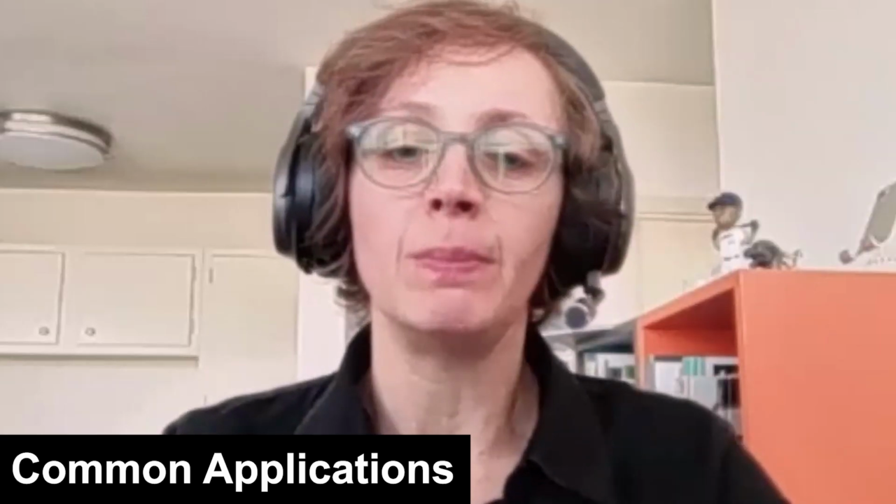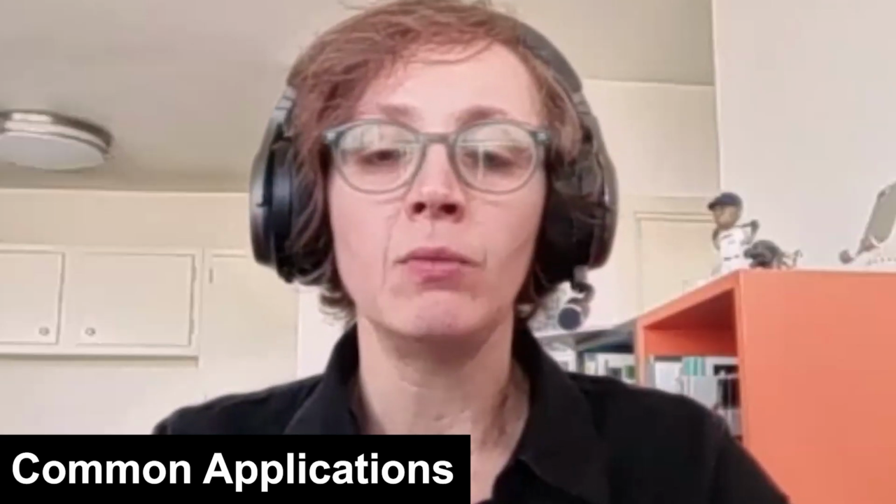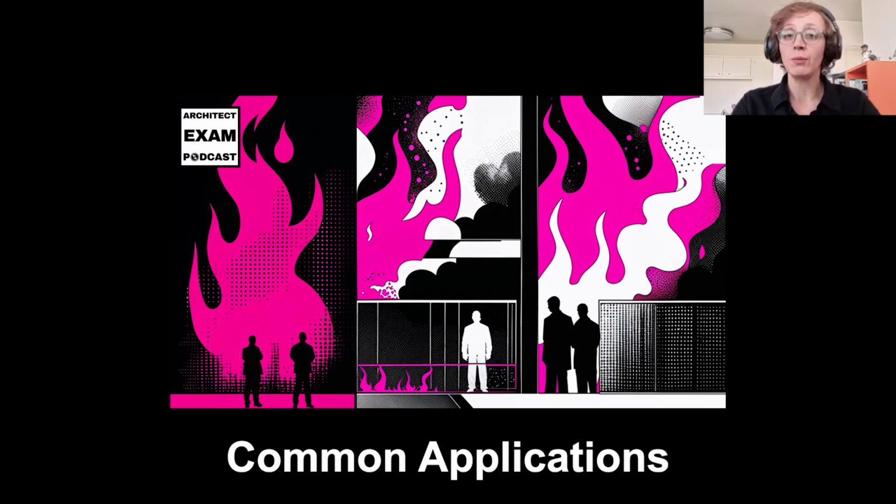Let's take a look at where you'll typically find each type of these walls in different buildings, because where these systems are used can really help you understand the concepts better. So let's start with healthcare facilities. Smoke barriers are critical for creating areas where patients can be moved horizontally. This is when we're creating smoke compartments within a building. And if you look at your Code Illustrated book, it does show that smoke barriers typically are used in healthcare facilities. Fire barriers surround exit stairs and shafts, and fire partitions can separate patient rooms.